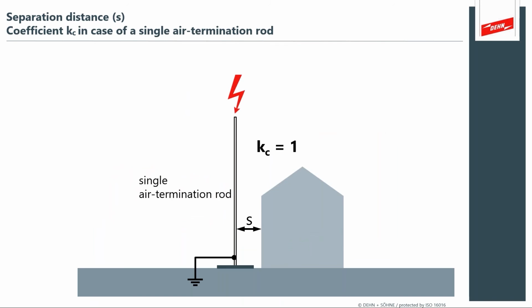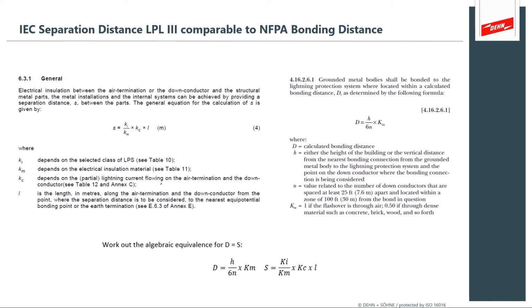So here we've got a nice illustration showing an air termination rod separated from your victim with sufficient spacing to avoid side flash. And what we see in NFPA is what's called bonding distance. It's essentially the same thing, and we've been able to show algebraically that the bonding distance D is actually the same effect as separation distance. And that's what the NFPA standard dictates, is that if your down conductor system runs adjacent or next to or near to metal bodies, you have to connect to it or provide sufficient spacing away from it.